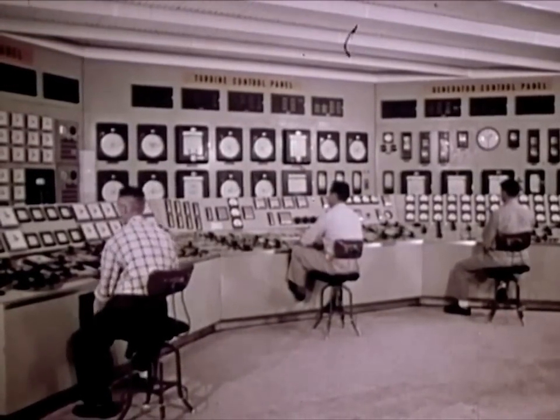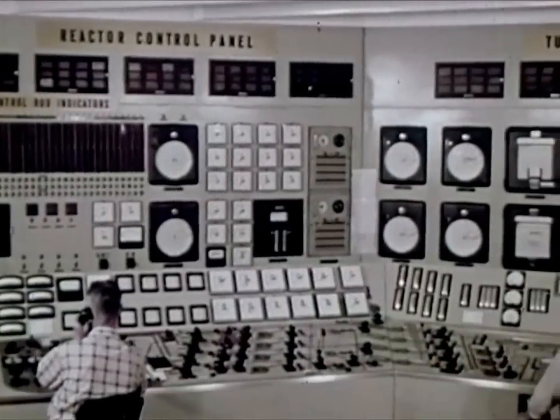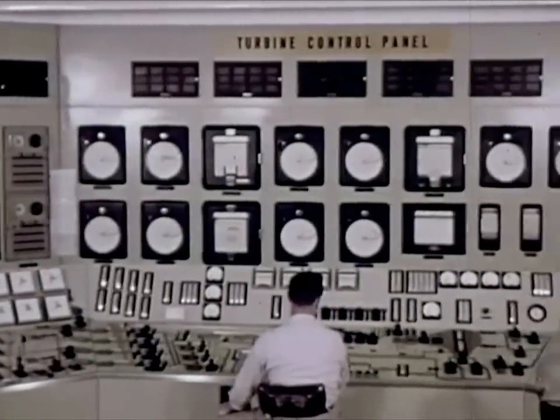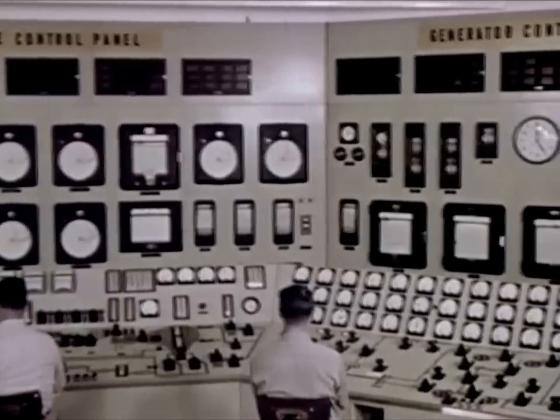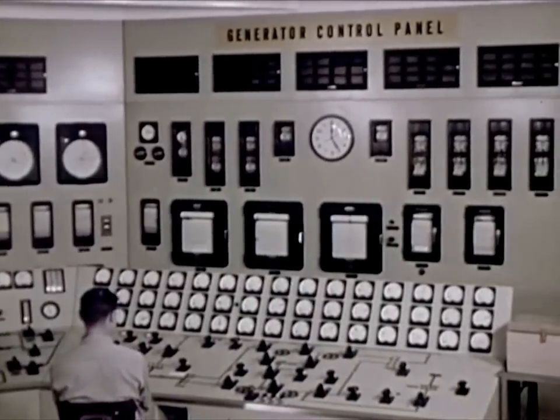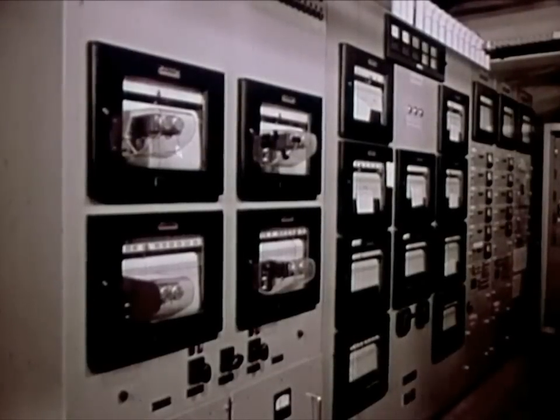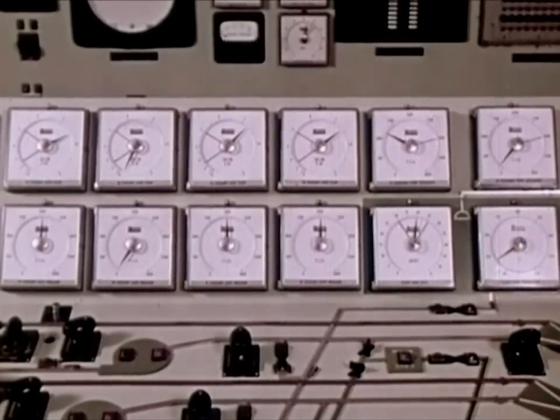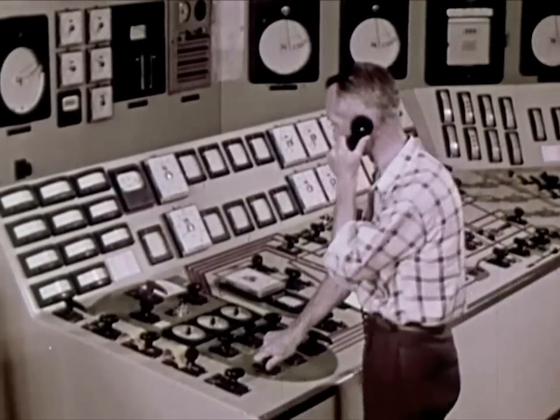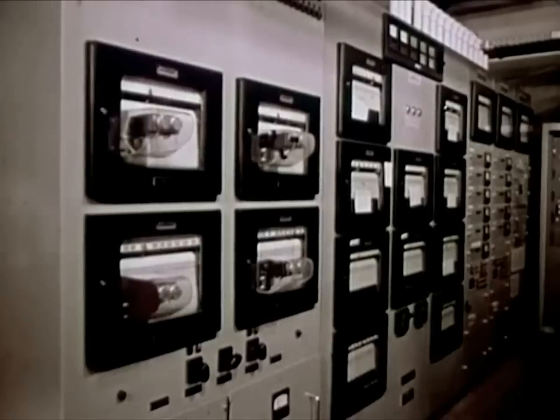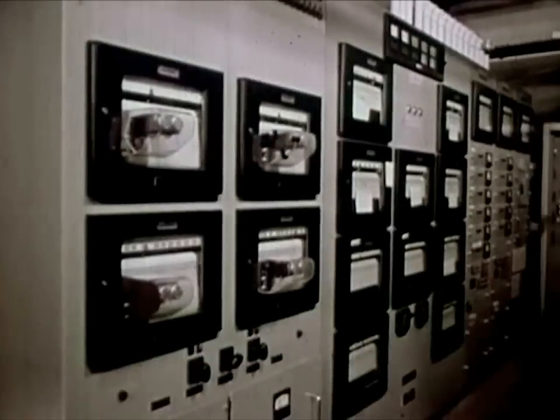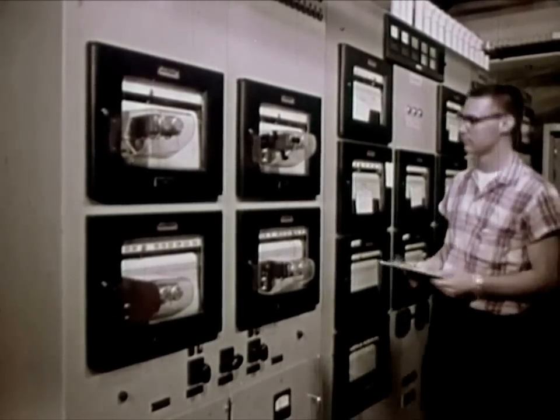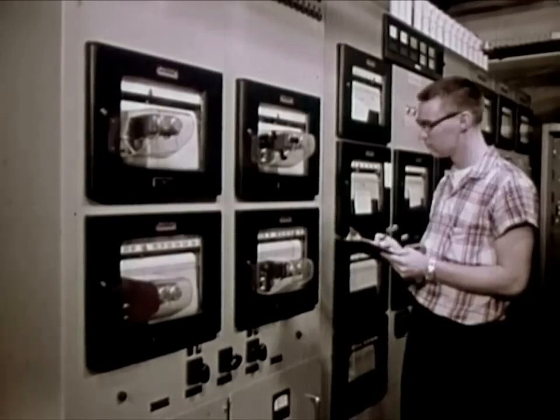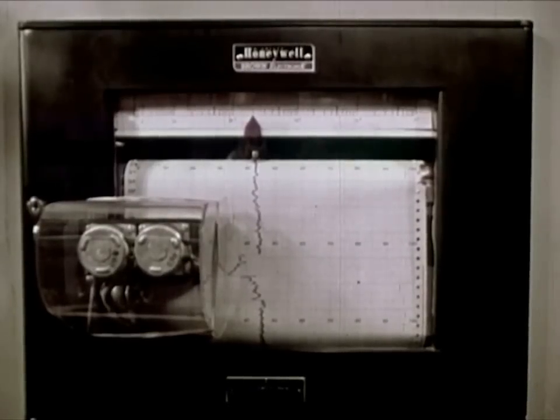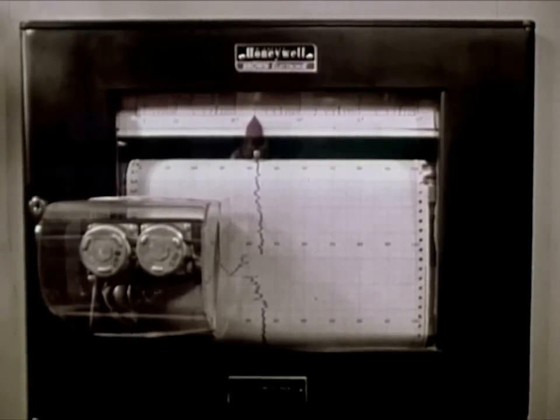Control of the operation of the plant is naturally divided into three parts: reactor, steam generation, and power generation. In addition, extensive instrumentation will provide a vast amount of information never before available. Among the continuous readings taken are water pressures, temperatures, flow rates, and power level in the reactor. In keeping with the developmental nature of the plant, a large part of the instrumentation is provided for indicating and recording design information and unusual events, and is not necessary for normal operation. Typical of this type of instrumentation is the extensive system designed to detect and locate fuel element failures.